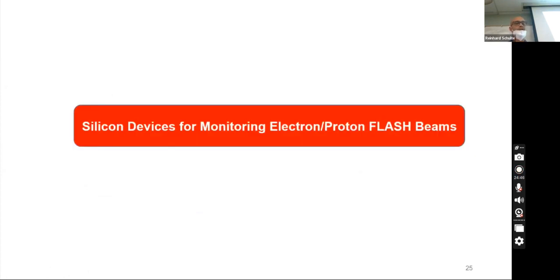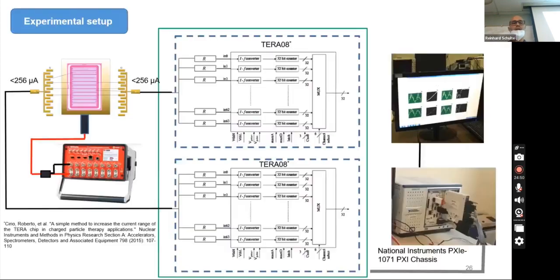And finally, I would like to introduce the silicon device for monitoring electron and proton FLASH beams. We also use the same detector, the LGAD strip, segmented, with 2.2 millimeter square of active area, being a segmented strip as you see here. We can read out this sensor with custom electronics that was developed by our group. It's a current to frequency converter called Tera08, based on a recycling integrator architecture. So we are splitting the signal of the sensor into 64. Doing that, we are increasing the capability of the electronics so we can reach 256 microamps in each strip. So we have a very high range of integration.